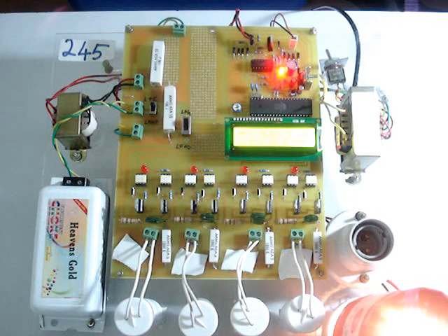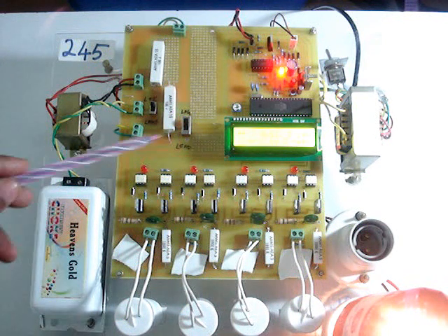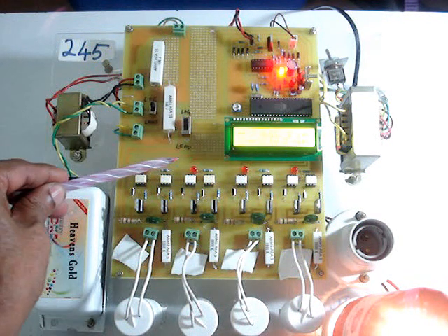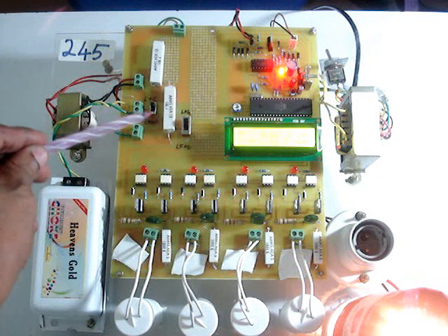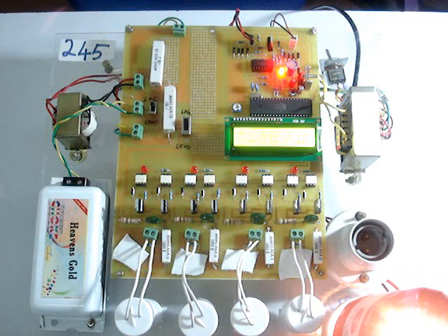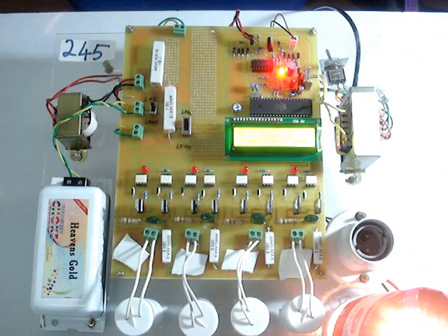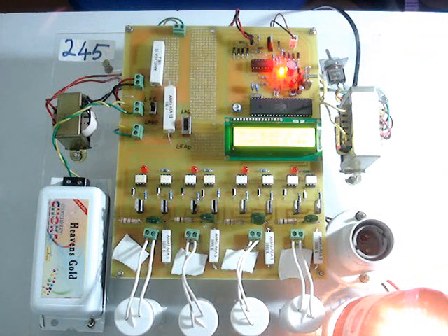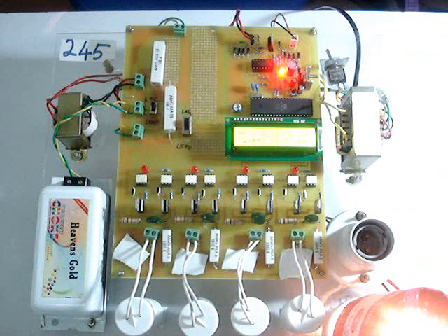Now you can see we have switched on an inductive load. The switch positions are indicated here: there is the lag position and the lead position. And of course, we will come later to the unity power factor position, whereas the other one is for the capacitor and inductor power factor. Now with one choke, it gives us a power factor reading of 0.61, where I is lagging by 2 to 3 milliseconds, a lagging power factor.